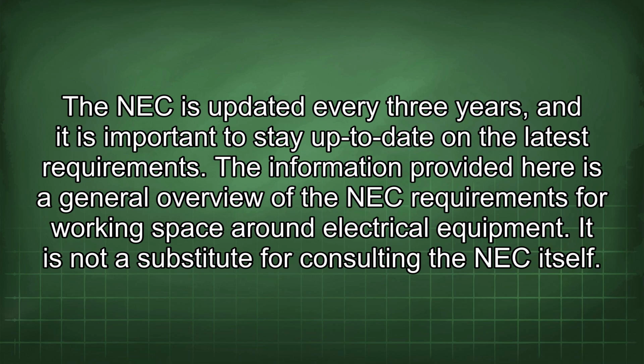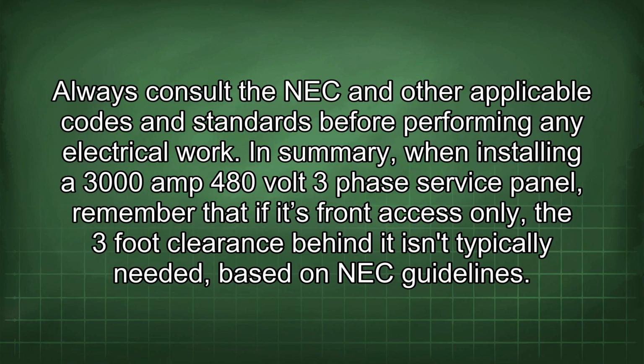The information provided here is a general overview of the NEC requirements for working space around electrical equipment. It is not a substitute for consulting the NEC itself. Always consult the NEC and other applicable codes and standards before performing any electrical work. In summary, when installing a 3000 amp 480 volt 3-phase service panel, remember that if it's front access only, the 3-foot clearance behind it isn't typically needed based on NEC guidelines.